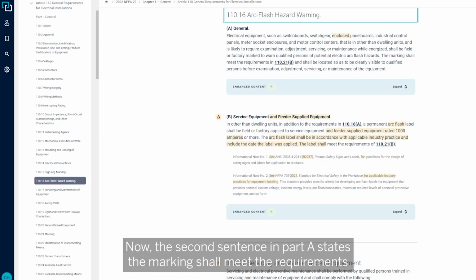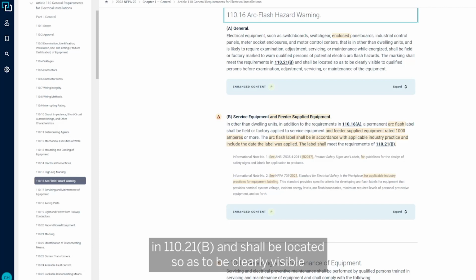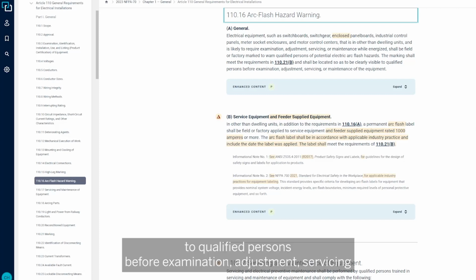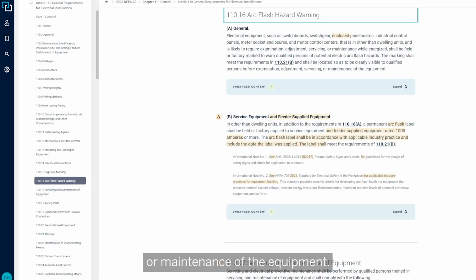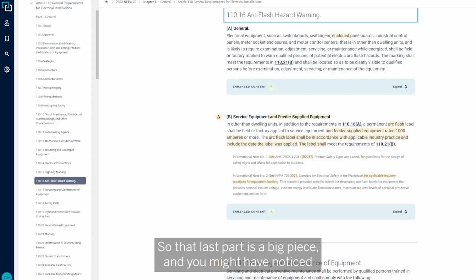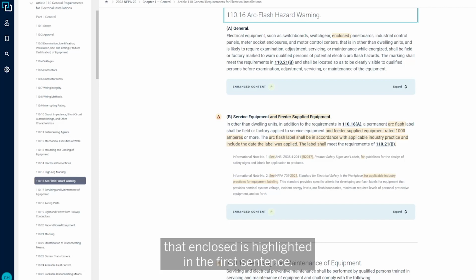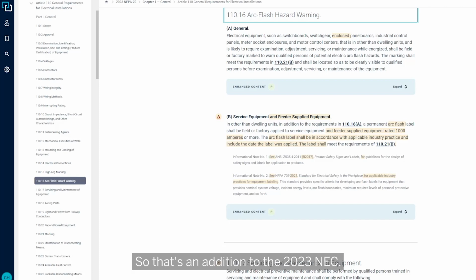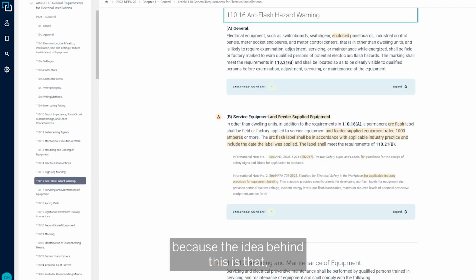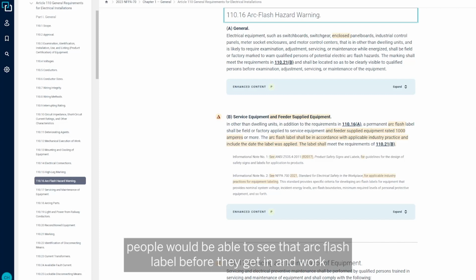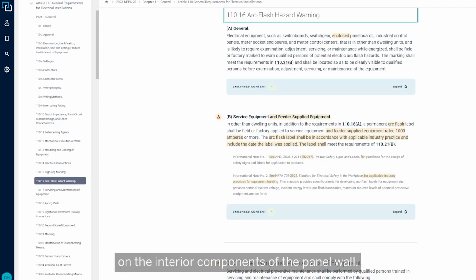Now, the second sentence in Part A states, the marking shall meet the requirements in 110.21(B) and shall be located so as to be clearly visible to qualified persons before examination, adjustment, servicing, or maintenance of the equipment. So that last part is a big piece, and you might have noticed that enclosed is highlighted in the first sentence. So that's in addition to the 2023 NEC, because the idea behind this is that people would be able to see that arc flash label before they get in to work on the interior components of the panel.